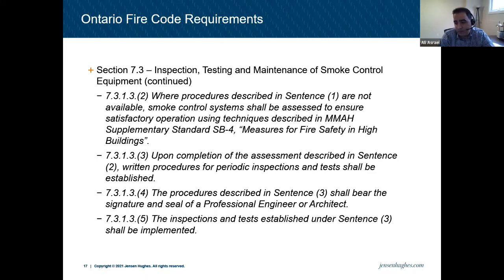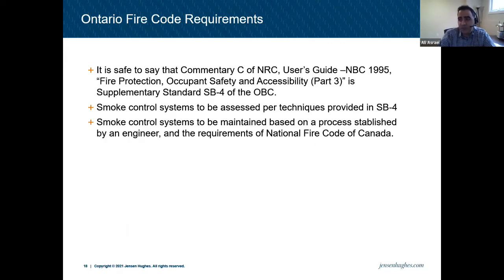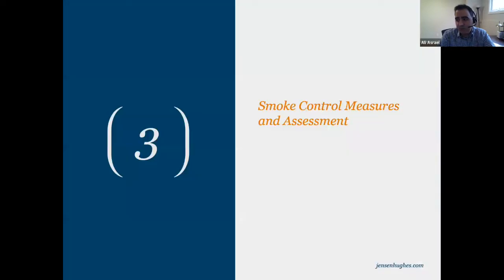And the last sentence says that obviously the inspection and test established under sentence 3 shall be implemented. So as I said, it is safe to say that the NRC is basically that SB4 that we have. So we have to assess the smoke control system based on some techniques that are provided in SB4 and put together a maintenance procedure, and moving forward, do that maintenance based on the procedure that is established for the system.